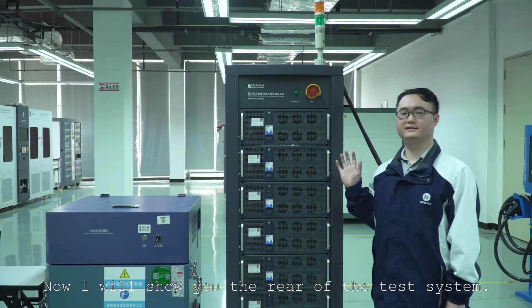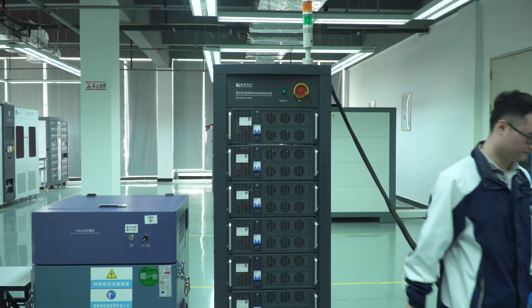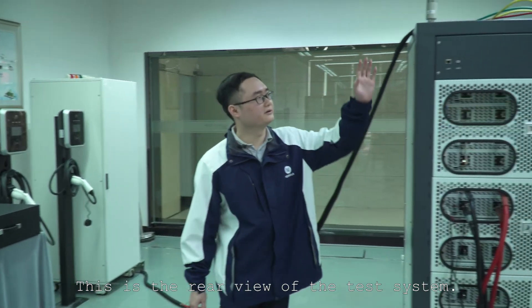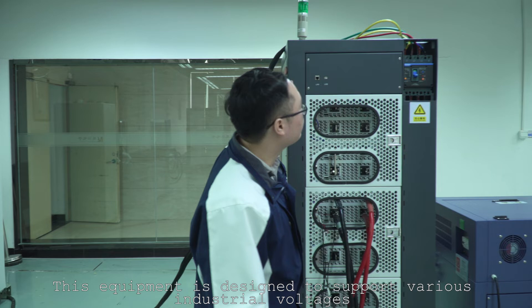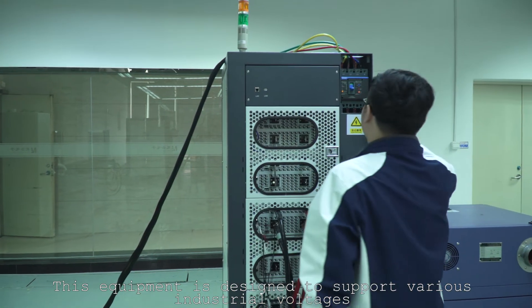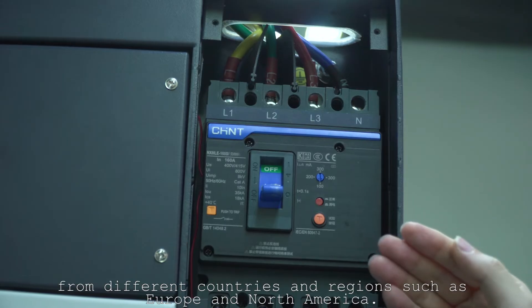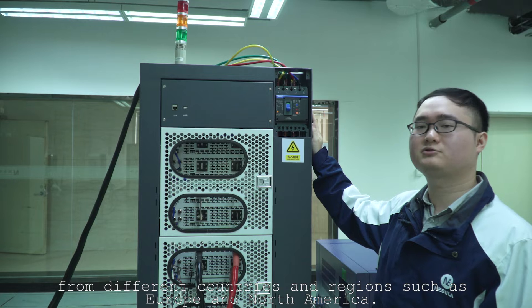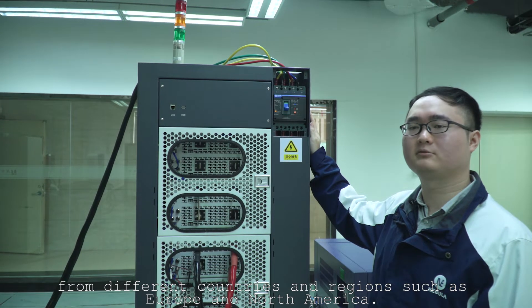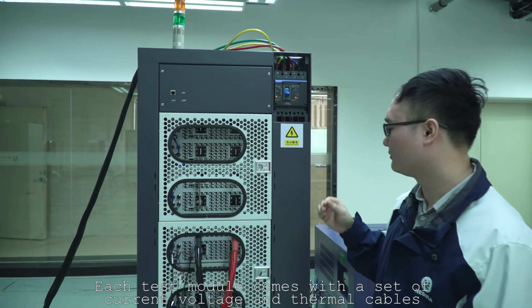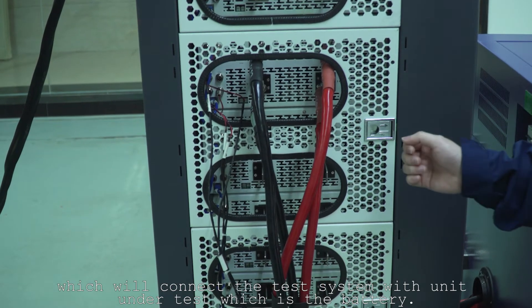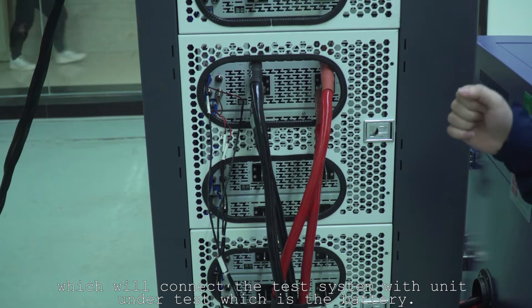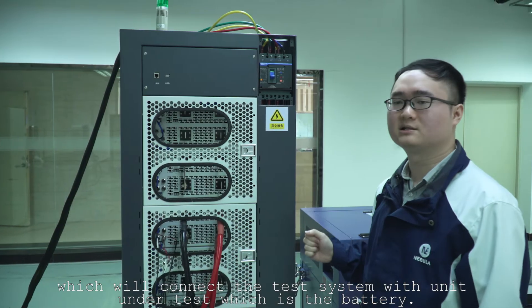Now I will show you the rear view of the test system. This equipment is designed to support various industrial voltage from different countries and regions, such as Europe and North America. Each test module comes with a set of current voltage and thermal cables, which will connect the test system with unit under test, which is the battery.